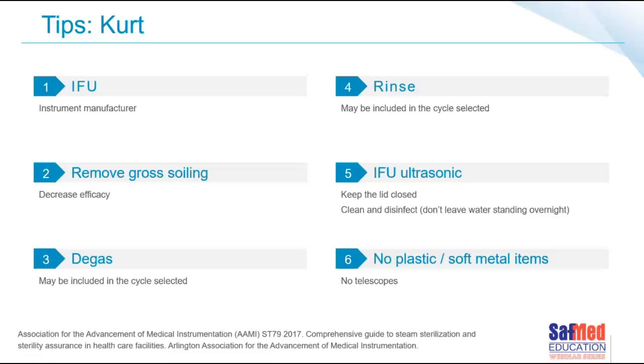I see you've got a point on number 6 about not mixing certain metals and not putting certain types of items in the ultrasonics. Teach us some more about that. Yes. So as in the manufacturer's instructions for use, it will state what you shouldn't put in, and the instruments' manufacturer's instructions for use, like I mentioned earlier, will tell you what can be put in an ultrasonic cleaner. But for the ultrasonic cleaner's instructions, please do not mix the plastics or soft metal with each other, meaning if there's aluminium, stainless steel with brass or copper, the staining of the instruments and the metals can move over to the next one and it creates damage to certain instruments. It can also, of course, damage the unit. So please do not mix those instruments.